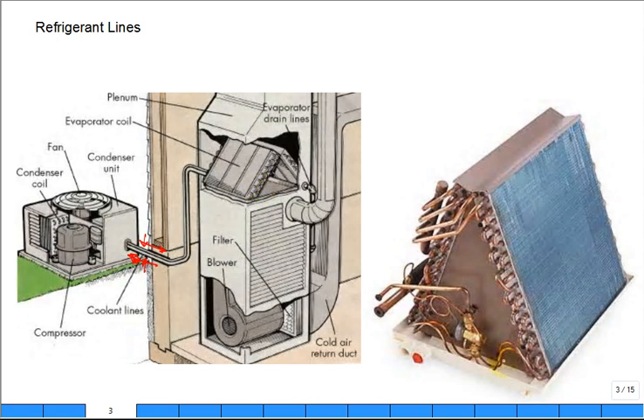Now this A-coil has a tray that collects the water. You see that tray? It has the shape of the coil so that when there's some condensate coming out of the air it drains down, collects right in here, but that whole section like under there is open so the tray just goes around. And that airflow goes up as we talked about.